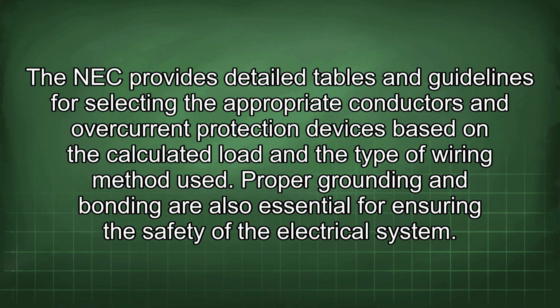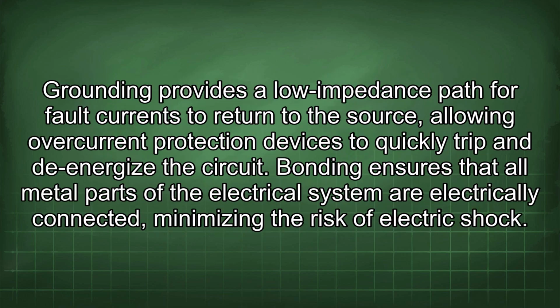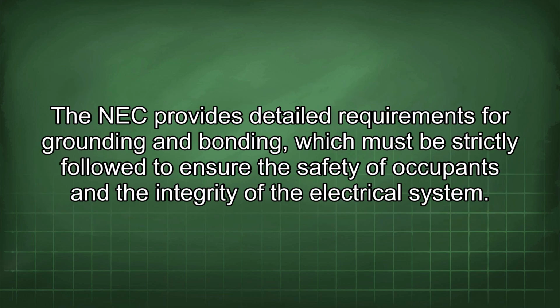Proper grounding and bonding are also essential for ensuring the safety of the electrical system. Grounding provides a low-impedance path for fault currents to return to the source, allowing overcurrent protection devices to quickly trip and de-energize the circuit. Bonding ensures that all metal parts of the electrical system are electrically connected, minimizing the risk of electric shock. The NEC provides detailed requirements for grounding and bonding, which must be strictly followed to ensure the safety of occupants and the integrity of the electrical system.